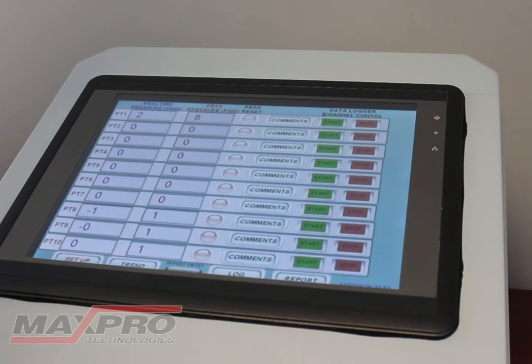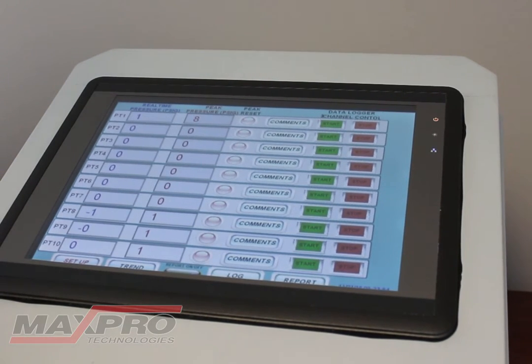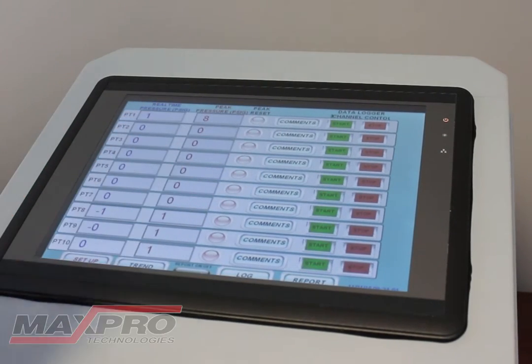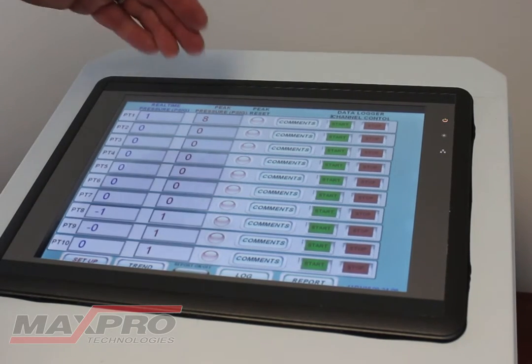Normally you would have the pressure transducer hooked up, and this particular unit comes with 10 30,000 psi pressure transducers. For today's demonstration, I've got a simulator box, so hooked up to pressure transducer 1, I can simulate the pressure.